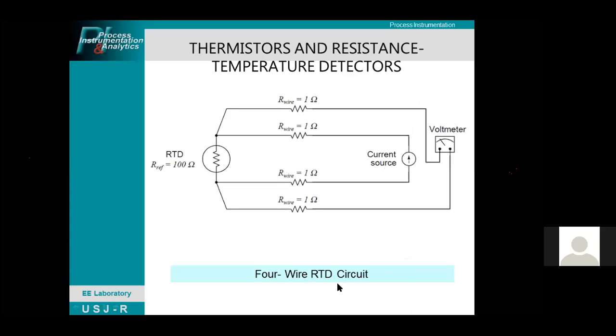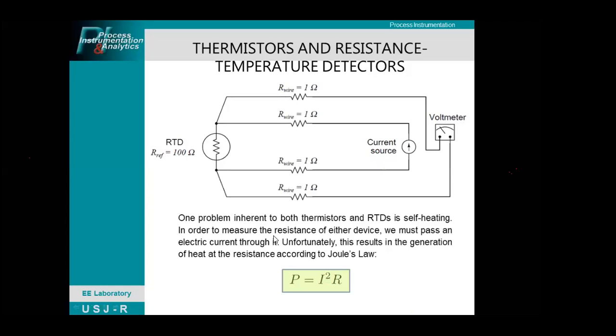Then for the 4-wire RTD circuit, this time you are connecting this one, then there's a current source applied, then there's a voltmeter across, measuring these terminals. That terminal and that terminal, you're measuring using this voltmeter.